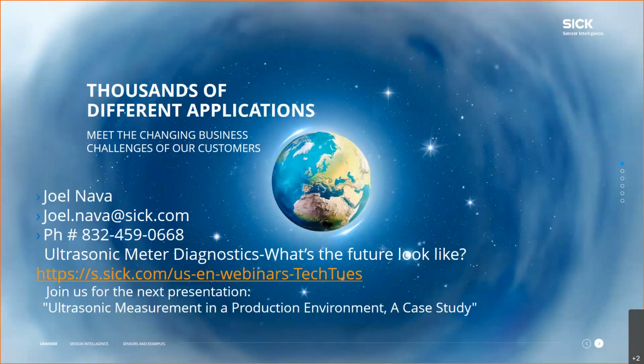We've got two more that we can probably get through quickly. The next one is, will the meter calculate theoretical SOS for comparison purposes to measured, and is that exposed via Modbus? Unfortunately, right now, and I can't talk a lot about this, I know this presentation is about what the future holds for the ultrasonic, I can't really talk about what other things are being developed. But right now, you can calculate speed of sound like you have in the past, and you can do some comparisons, but as far as doing live comparisons, that's not available currently.